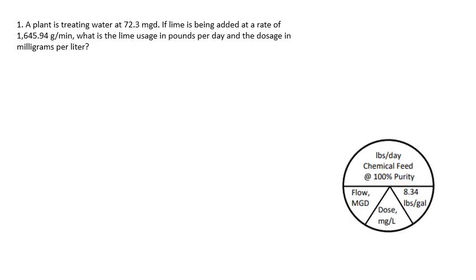Alright, question number 1. A plant is treating water at 72.3 million gallons a day. If lime is being added at a rate of 1,645.94 grams per minute, what is the lime usage in pounds per day and the dosage in milligrams per liter?